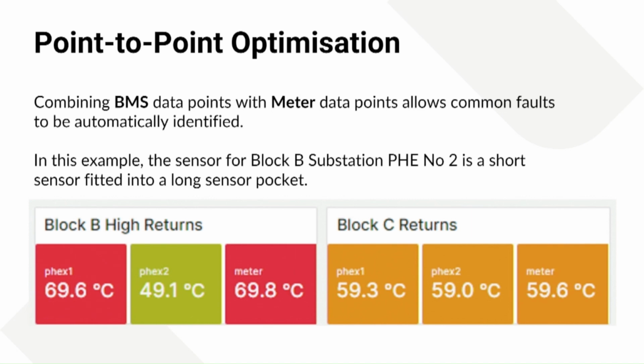Two plate heat exchangers on a substation with a heat meter. If you look at the plate heat exchanger sensors versus the heat meter sensor, they don't match - they're different colours. That's an alarm that's been going for years with no one knowing. Across this site we had meter sensors loose, and no one knew until you looked at them against the BMS sensors - straight away it's clear something's not right. They should all match, all the same colour, like on the right.